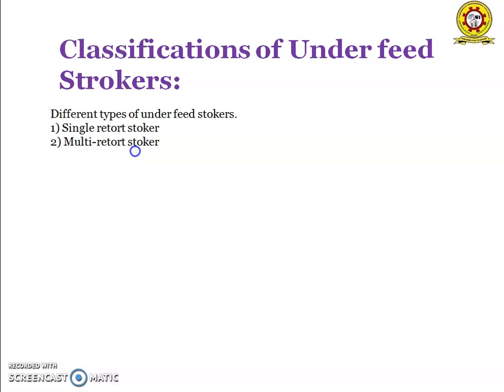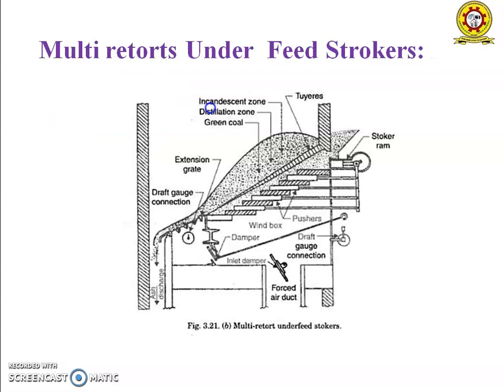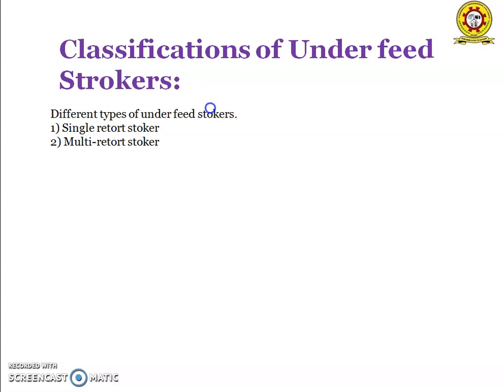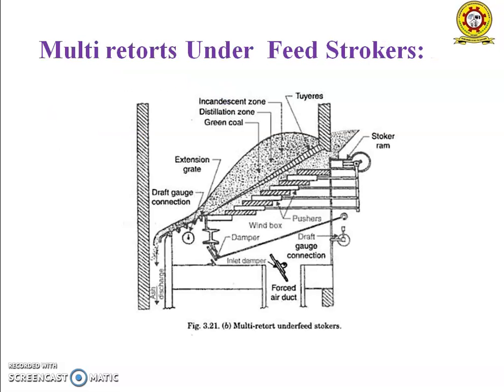The distribution rams then slowly move the entire coal bed down the length of the stoker. The slope of the stoker helps in moving the fuel bed downwards. The primary air enters the fuel bed from the main wind box situated below the stoker. Partially burnt coal moves onto the extension grate. The air entering from the main wind box into the extension grate wind box is regulated by the air damper. The advantages of single retort stoker: a wide variety of coal can be burned; operation cost is very low.